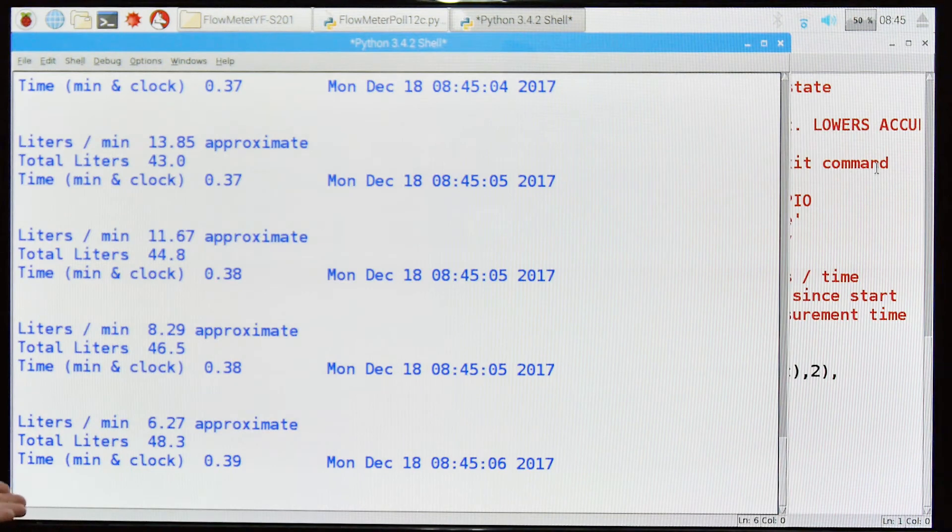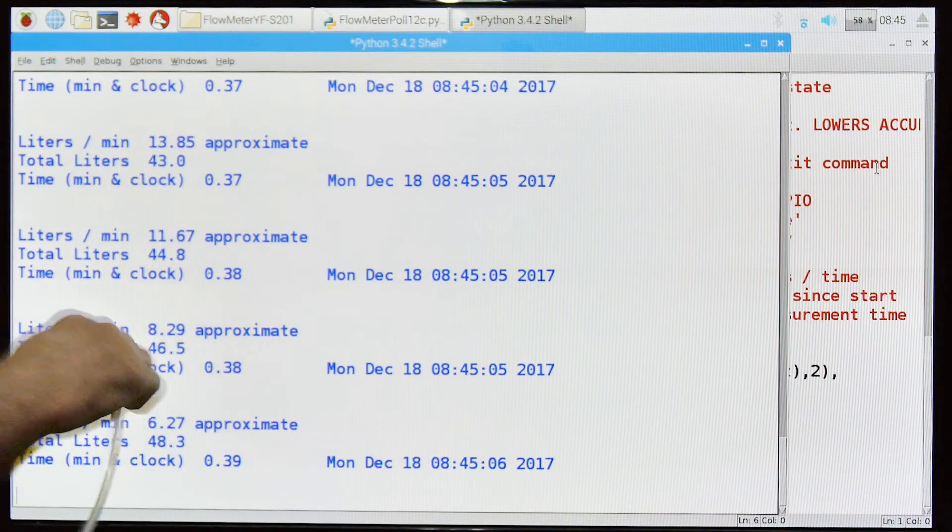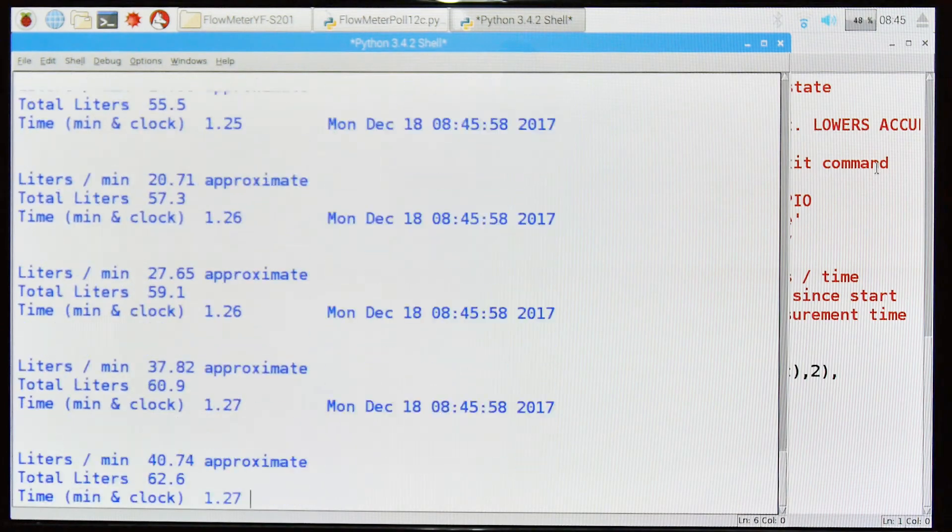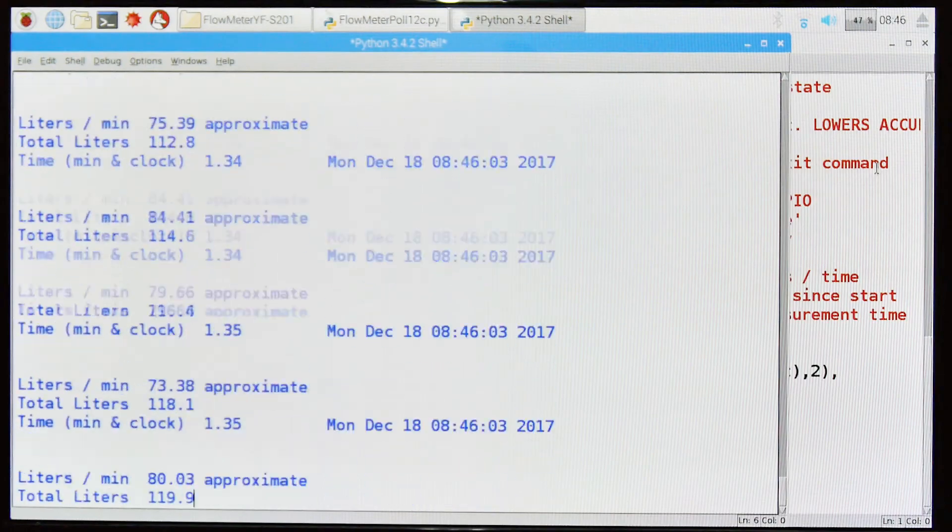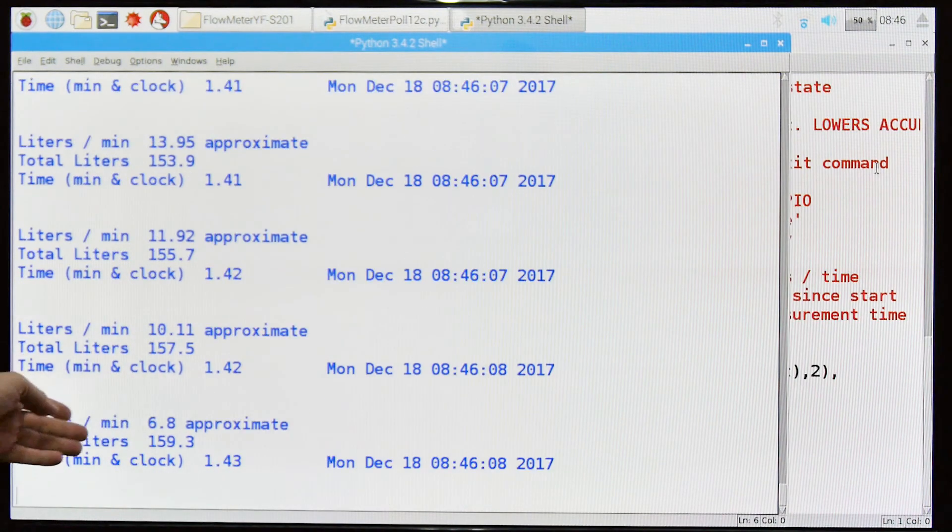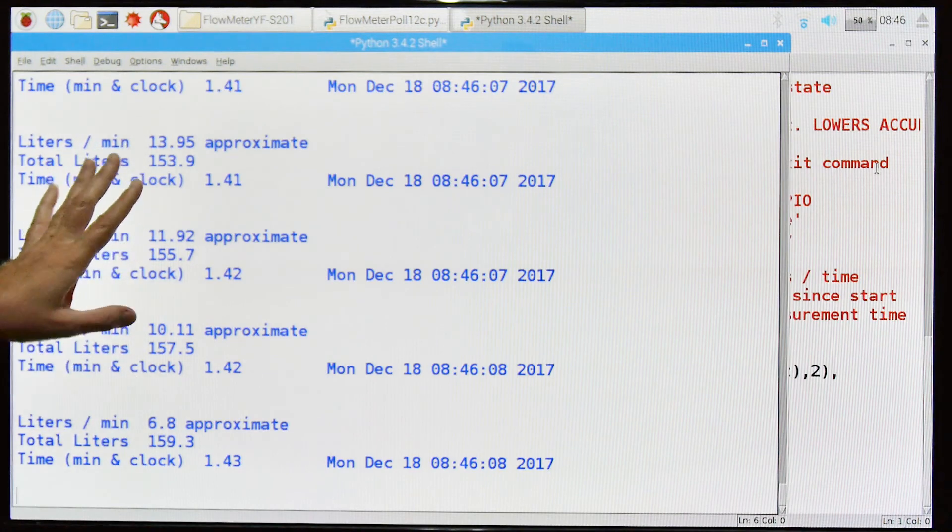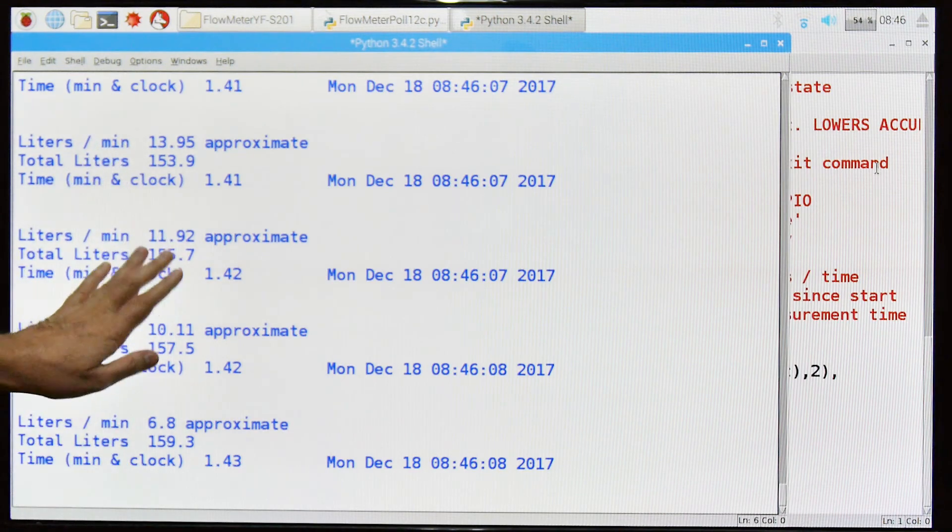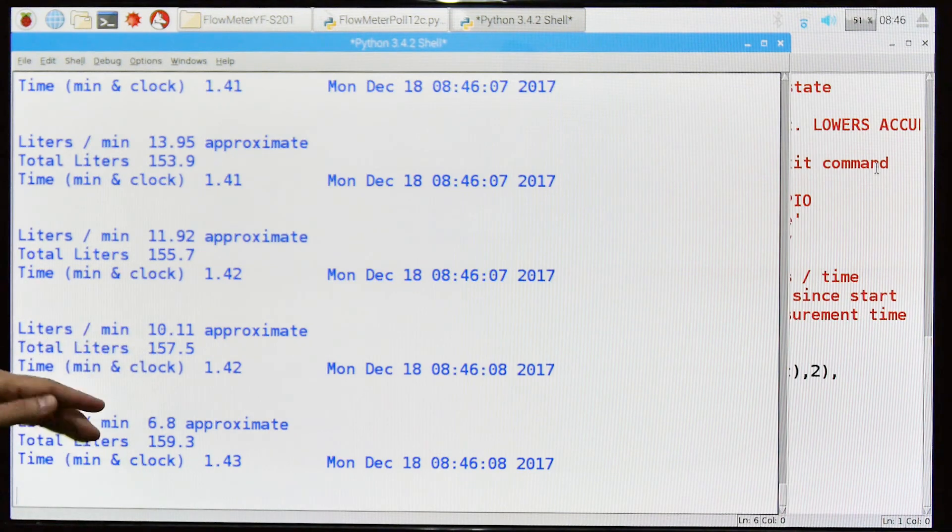So you can see that it's not running. If the impeller has stopped, there's no readings. Let me do it again. You'll notice that the faster the impeller turns, the more readings you get. And when the impeller stops, we're not getting false readings anymore. So with this polling version, and this is again an impulse driven version, you are free from the worries and issues of a stopped impeller.